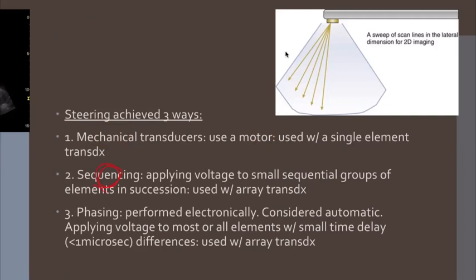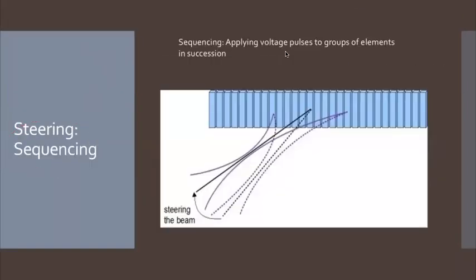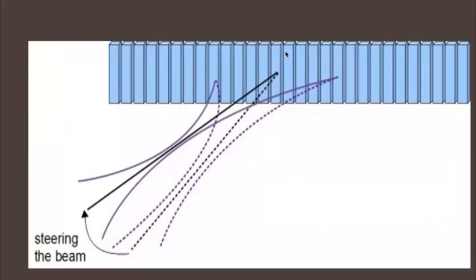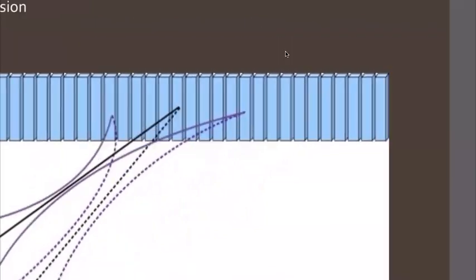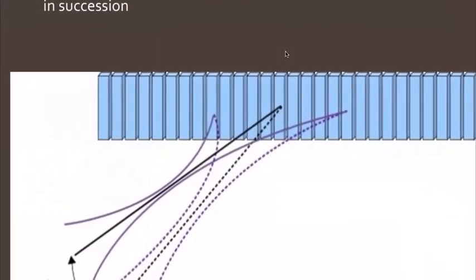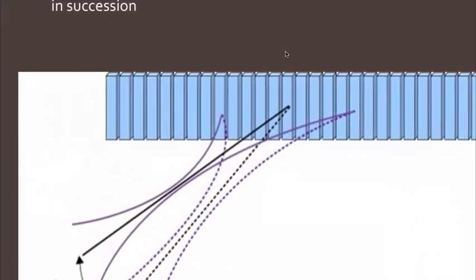And so I'll show you guys a picture that helps you understand this, and you also have a picture I'm going to reference in the book. So here's an array transducer, and there's a bunch of PZTs in this. All these little blue rectangles are PZTs. What's going to happen is electricity will go to, let's say, 5 of those PZTs. So electricity goes to all 5 of those at the same time, and it steers the beam in a specific direction.